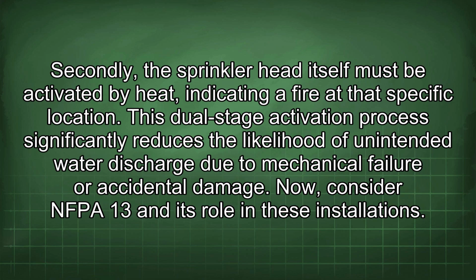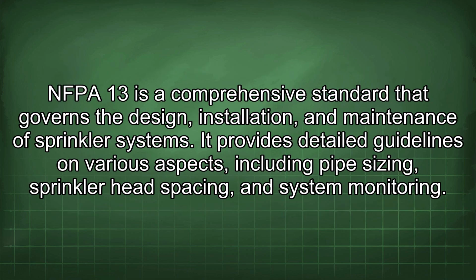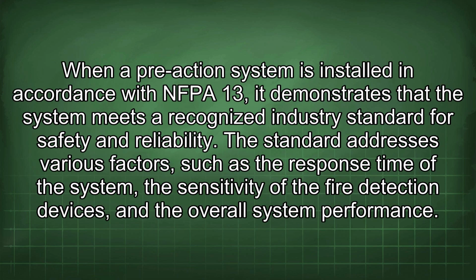Now, consider NFPA 13 and its role in these installations. NFPA 13 is a comprehensive standard that governs the design, installation, and maintenance of sprinkler systems. It provides detailed guidelines on various aspects, including pipe sizing, sprinkler head spacing, and system monitoring. When a pre-action system is installed in accordance with NFPA 13, it demonstrates that the system meets a recognized industry standard for safety and reliability. The standard addresses various factors such as the response time of the system, the sensitivity of the fire detection devices, and the overall system performance.